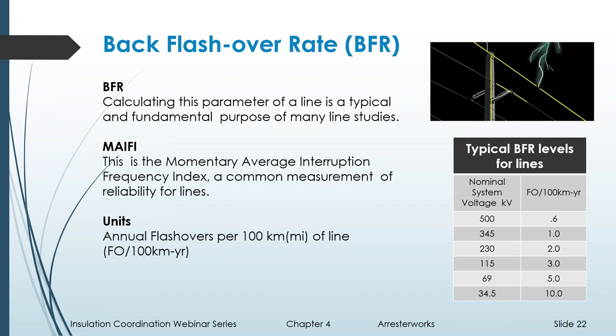If your goal is to determine the backflash rate of a line, you can use this graph here as a guide. These are typical numbers that you might get. You can see that the lower the system voltage, the higher these backflash rates can get. We usually do studies for trying to improve backflash on the lower voltage systems, not on the very high 500 kV systems. It doesn't mean you can't, but it's usually on a lower voltage system.